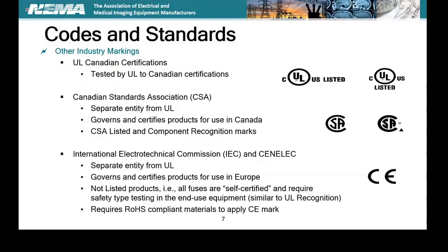Yeah, I know there was a discussion on one of these code cycles where we said, listing, product testing, evaluation of the listed product shall be in accordance with applicable product standards recognized as achieving equivalent and effective safety for equipment installed to comply with this code. And then we referenced the OSHA NRTL program and things like that. But if it's harmonized, you could pretty much find out if it was listed at CSA under the standard. If it was a harmonized standard between Canada and US, it would be acceptable to an AHJ. Yeah.